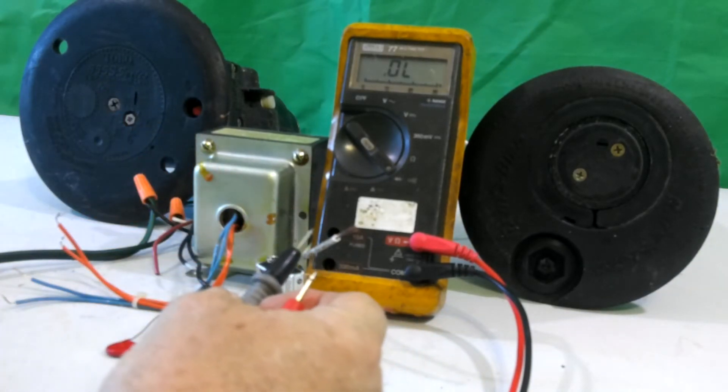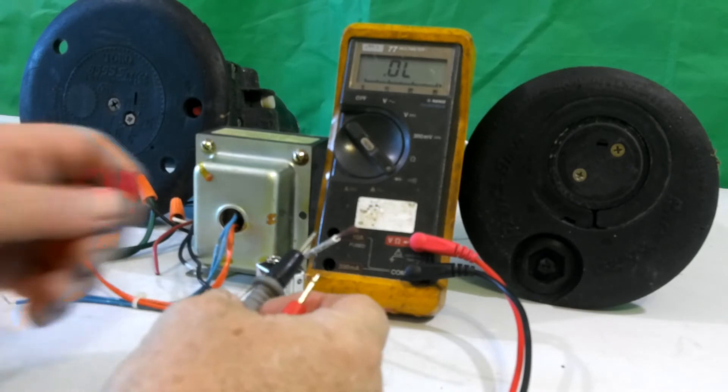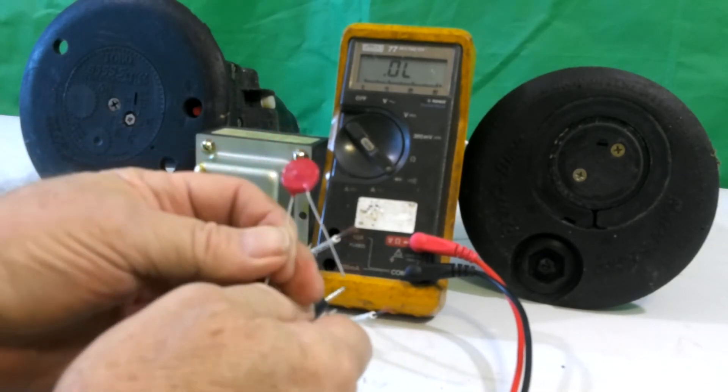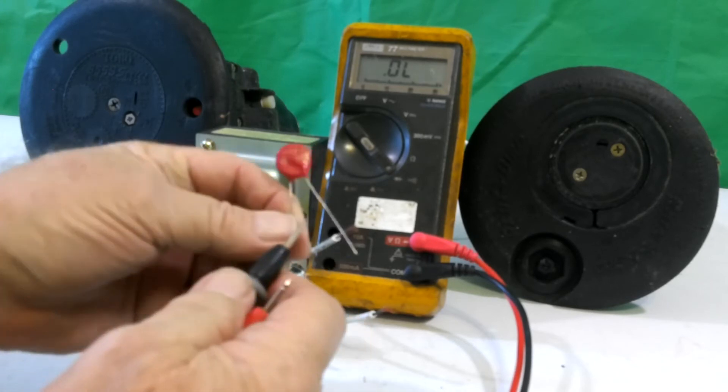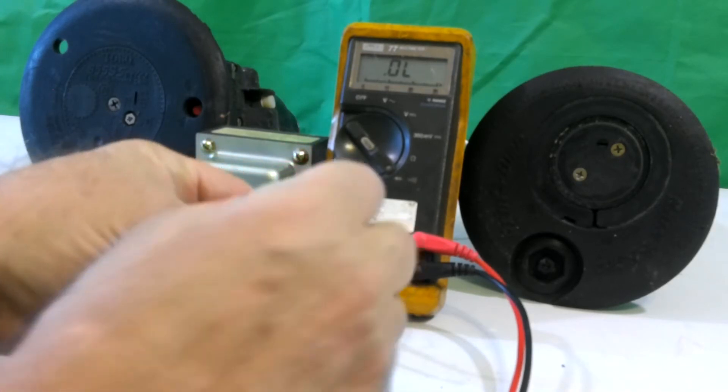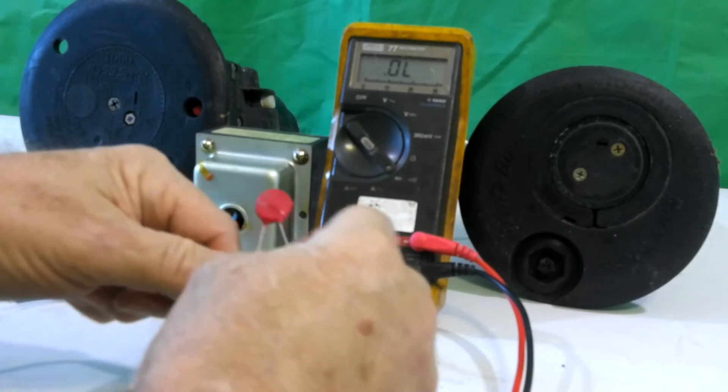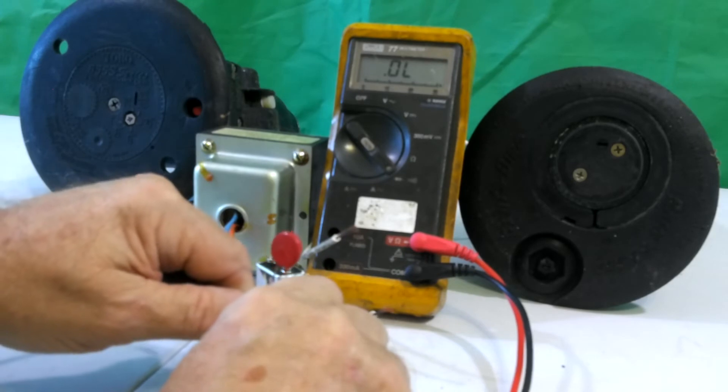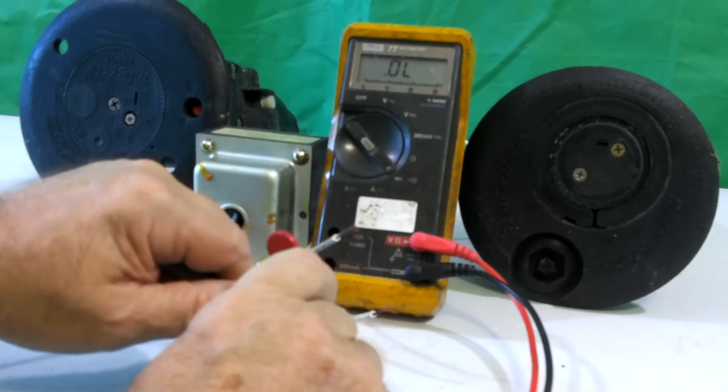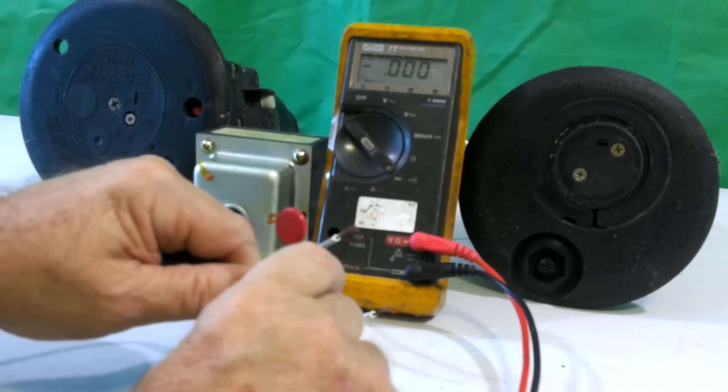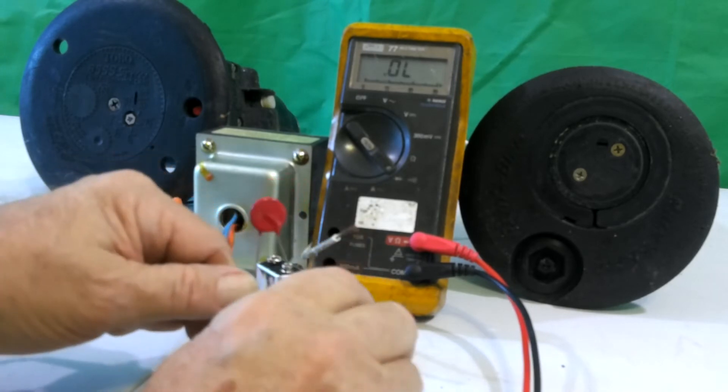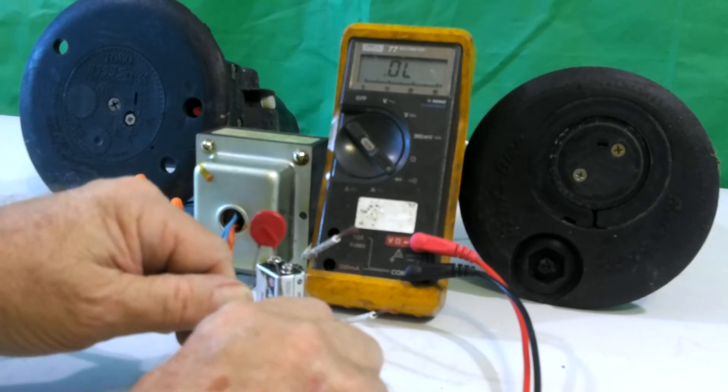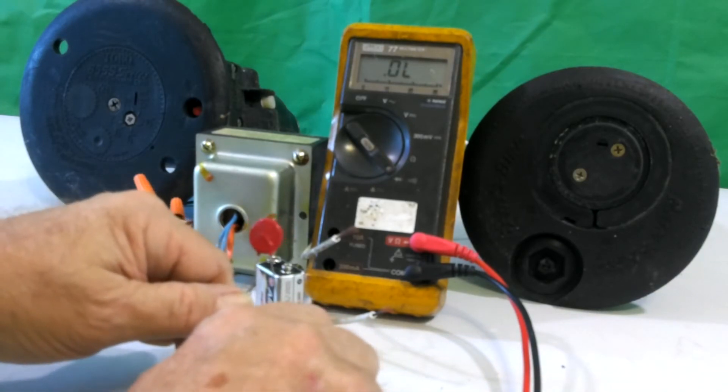The next thing I can test is a lightning protection device called a metal oxide varistor, or MOB or MOV. To do that, again in continuity, we put one probe on one leg, another probe on another leg. You'll notice there is no reading. If I had a reading showing a direct short, it means that this metal oxide varistor is shorted out and that whatever that's connected to is probably not working because it shorted the ground. That's how we would test for that.